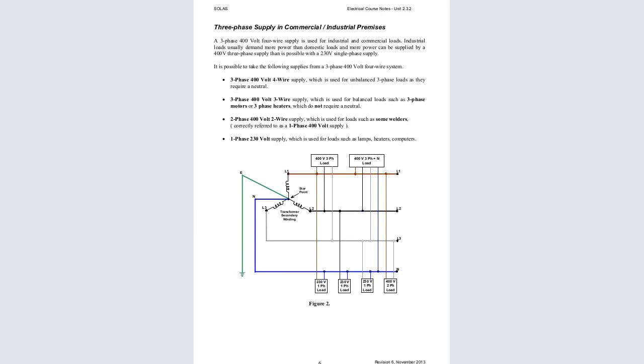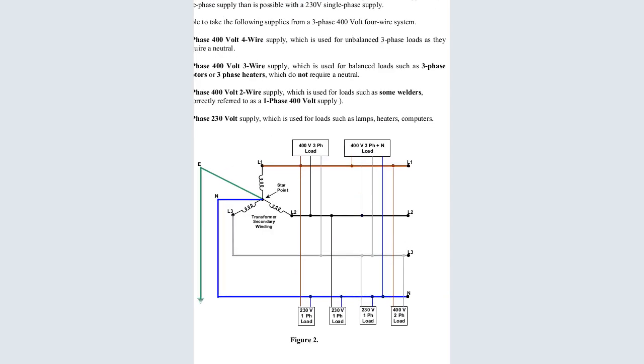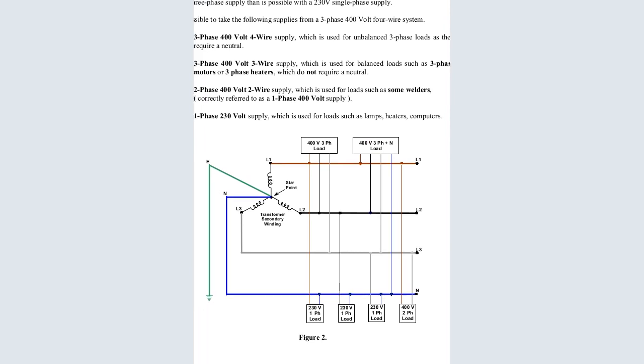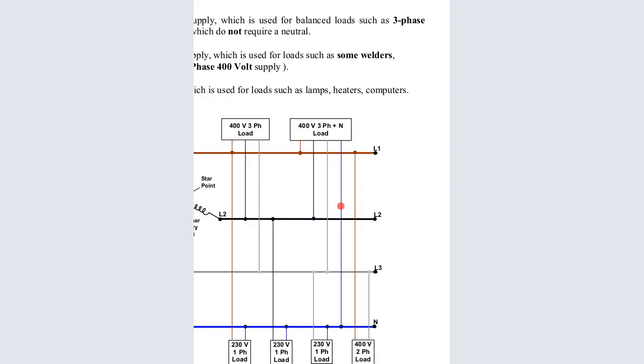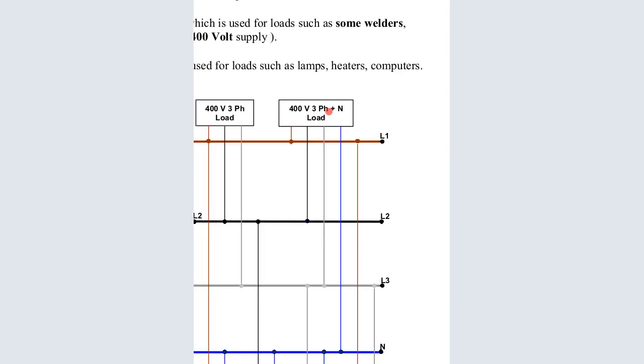The first load that we can supply is a 3-phase 4-wire supply that is used to supply unbalanced 3-phase loads, as they require a neutral. So you can see here, this load plus neutral. You can see where my red is pointing. I hope you guys are seeing. This is now the 3-phase neutral. I'm zooming so that you can see, this load in a rectangular box is written for 400 volts 3-phase plus neutral.